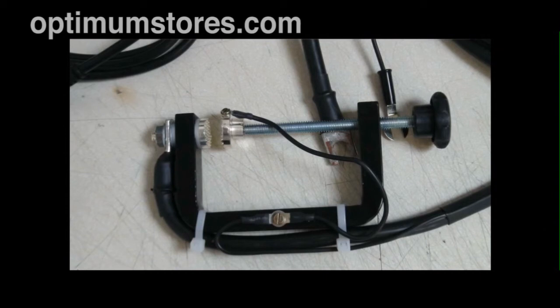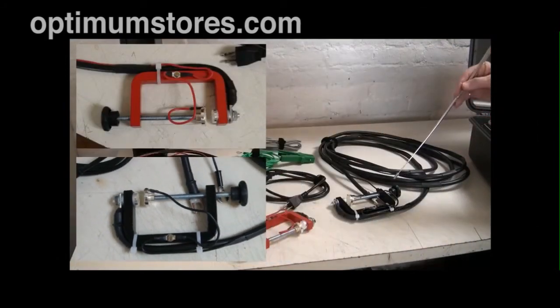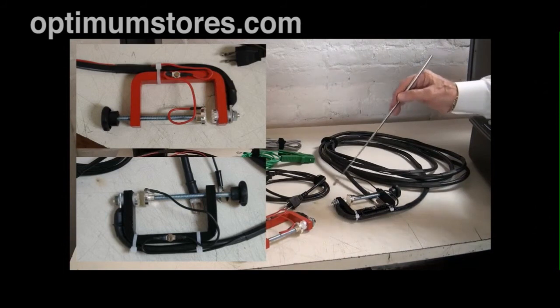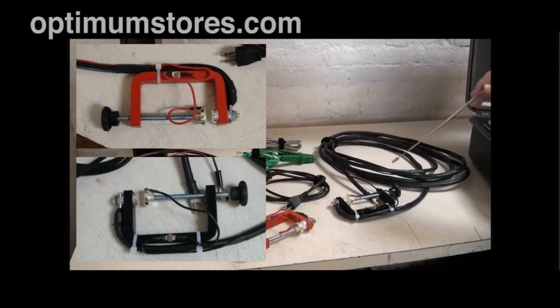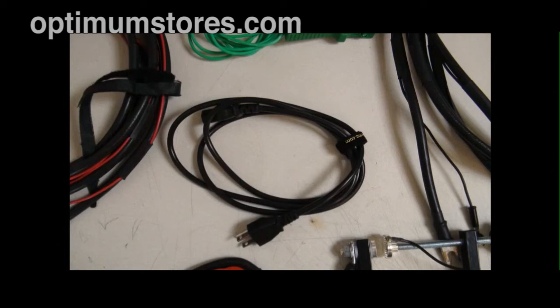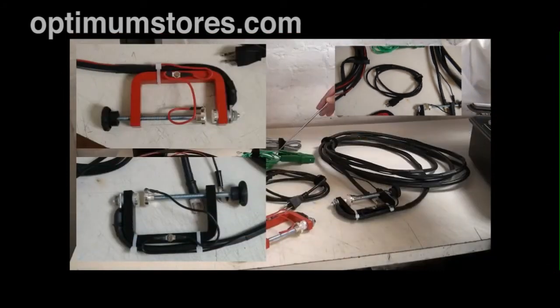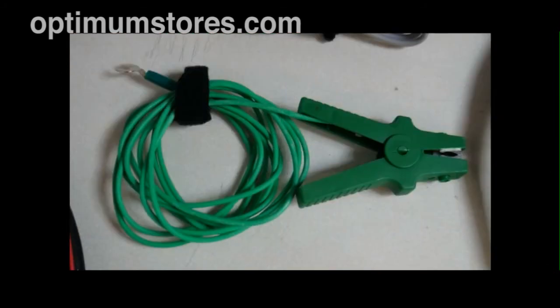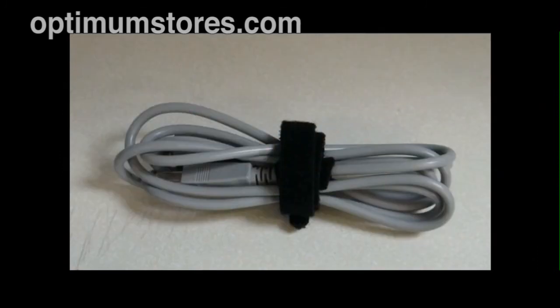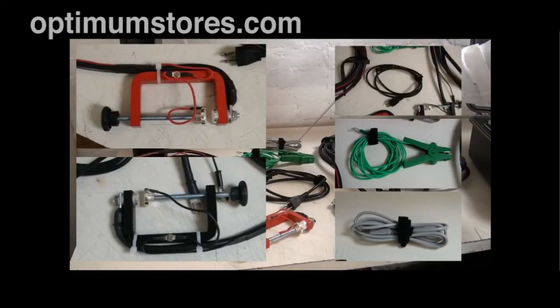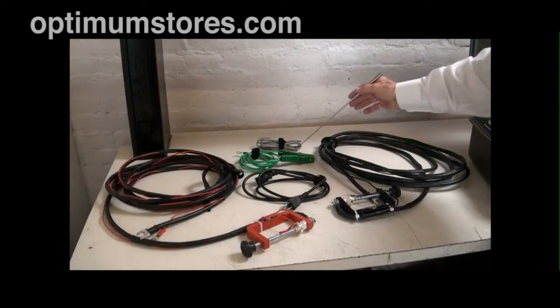If we know what the current is going through the test specimen, and we know the voltage across the junction, we can calculate the resistance. Because we have brought the sensing leads right out to the point of contact, it eliminates the resistance of the leads themselves. We have the power cord, and in the case of high inductive voltages, we have a grounding strap that can be put on the test specimen and brought over to the test box. And of course we have a USB port for downloading, and the cable.